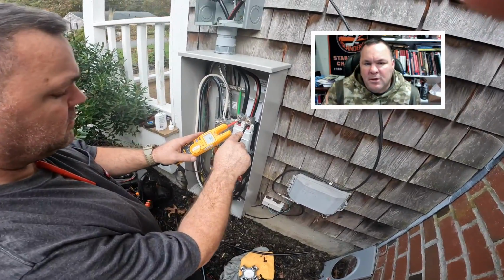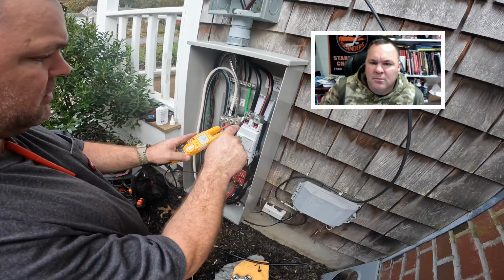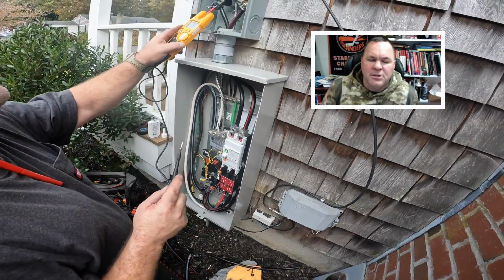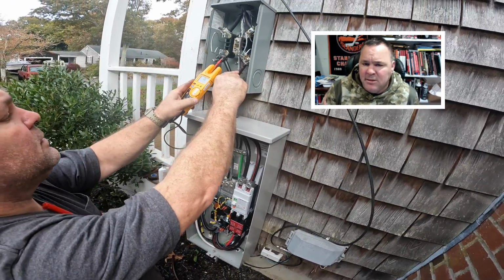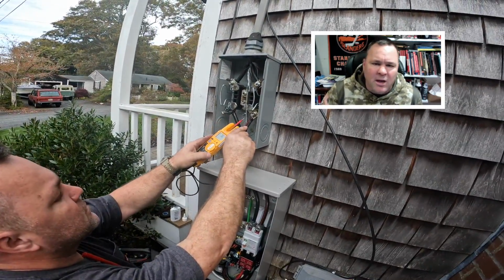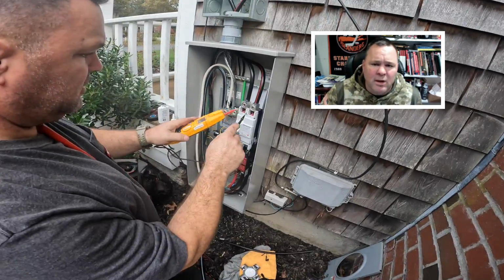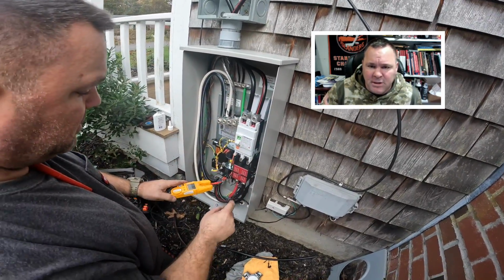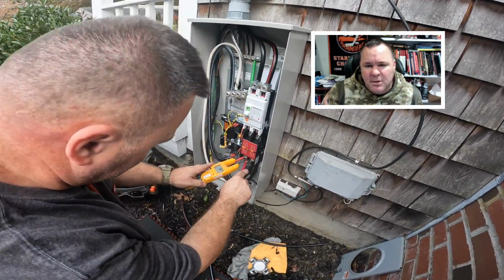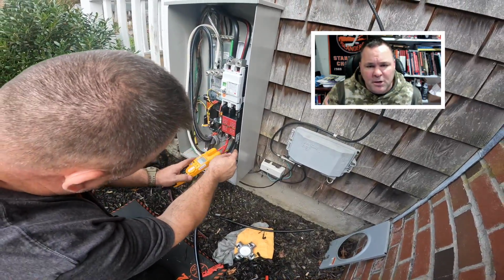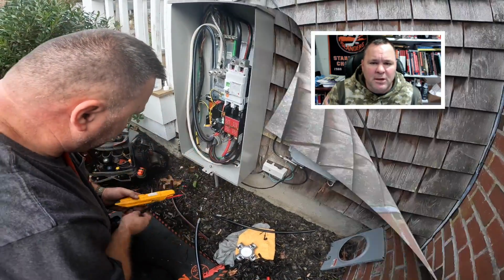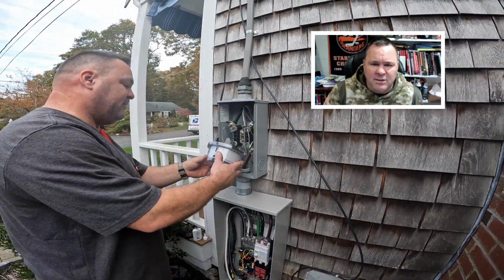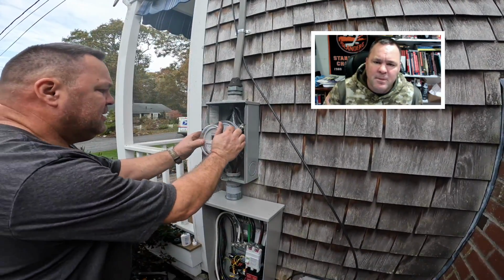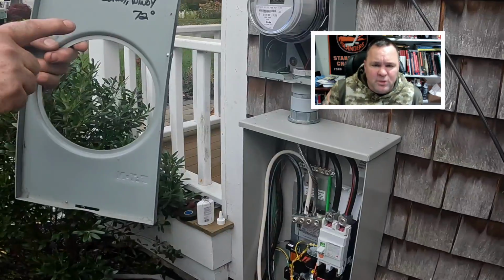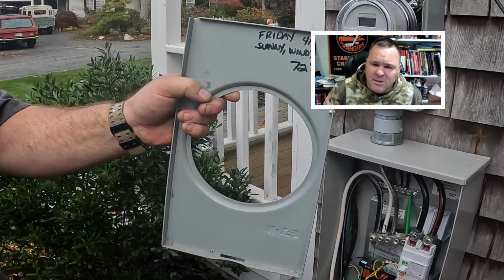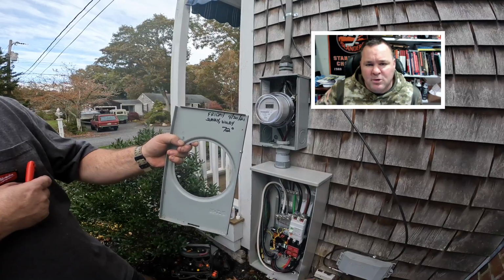I'm checking my work here with my T6 digital voltage display Fluke testers. I'm testing resistance, and I'm checking for continuity between any of my hot conductors and ground to make sure there are no faults in place that happened during the installation. Once I get the all clear, then I can put the meter in and re-energize the service to this house. So let's put the meter in, then let's turn on the main automatic transfer switch disconnect, and then the main disconnect inside the house, and all the power is back on.